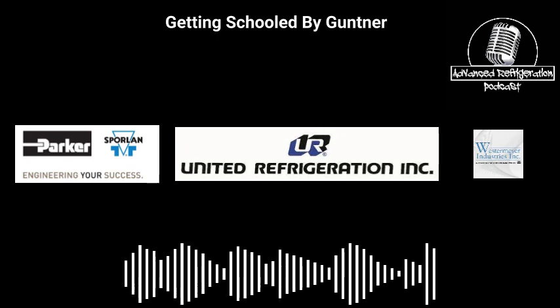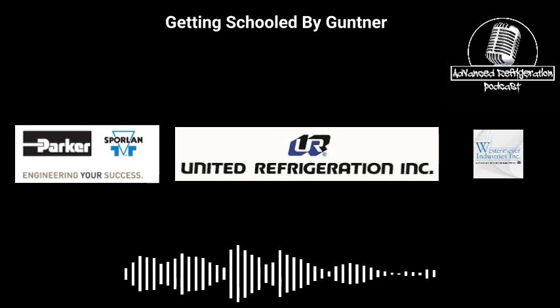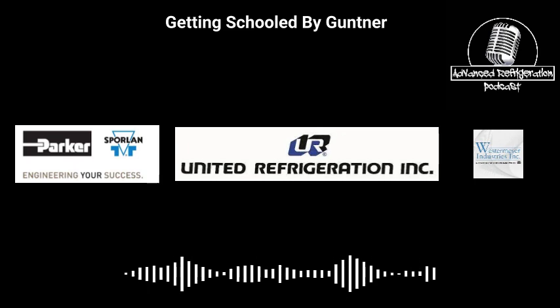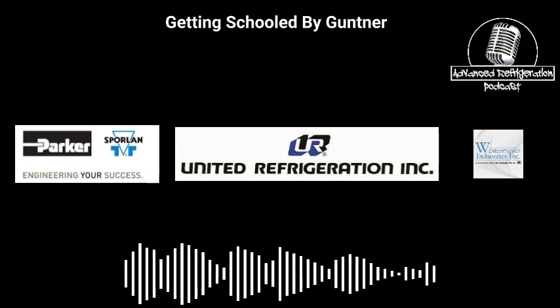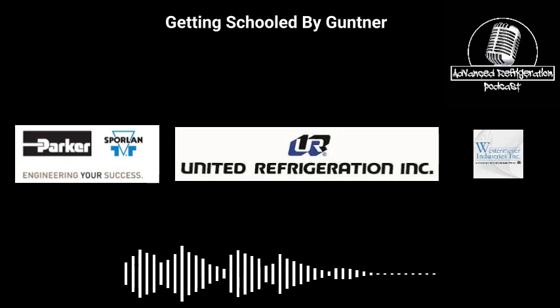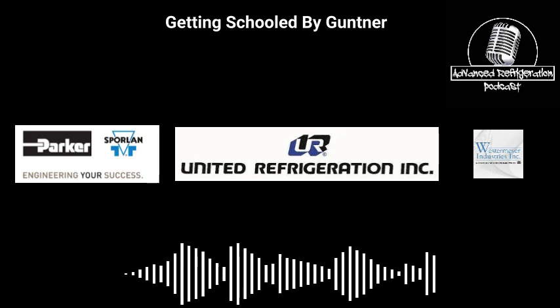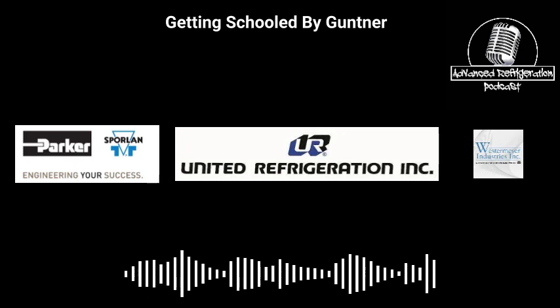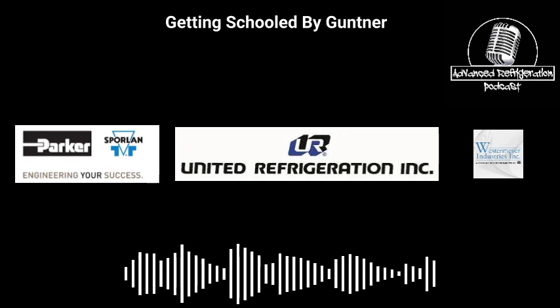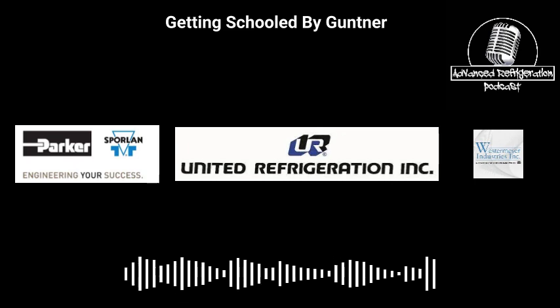When you speak of a bypass valve, what kind of valve are you speaking of? Like a three-way bypass valve. So in certain situations, you might want to bypass our unit depending on ambient temperature. The only time I've ever seen that is if you're dealing with a cascade and you're using part of the adiabatic as basically just a desuperheater. That's the only time I've ever seen that. Yeah, I'll be honest, I haven't seen it used too much, but I take that back, because there are a lot of our customers that do use it. For a lot of the dry cooler stuff, it could be used on a dry cooler as long as the temperature pressure sensor is installed. Okay. So it's just to bypass the unit if need be.